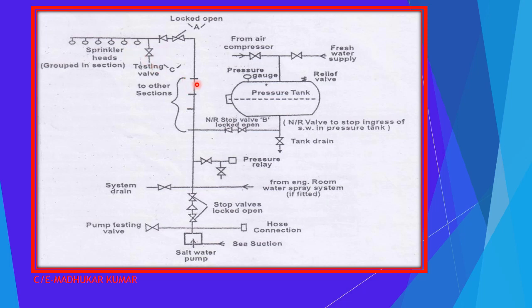Okay, and in the same way you can see the other sections are also installed over here. This is the pressure relay which is fitted on this. And if there is any engine room water spray system, you can have the connection from that also. The system drain line is completely drained. When the pressure drops to 5 bar, then your seawater pump will start. Here you can see the salt water pump or seawater pump. There is a sea suction, and once it is sensed, the signal will go to that and the water supply from there.